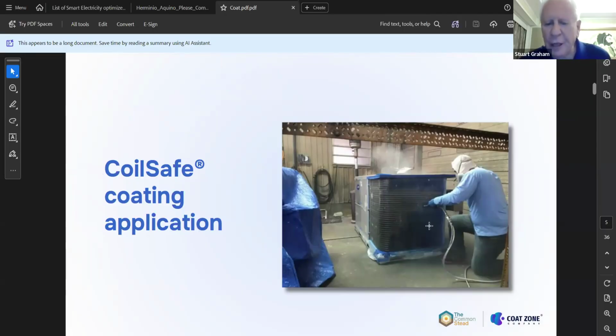As you'll see, we don't ever remove the coil. We simply remove enough panels, and in this case the fan, to get at the coil, which the manufacturers like because we never break the refrigerant line or any solder joints. We ensure that the integrity of the unit remains intact.